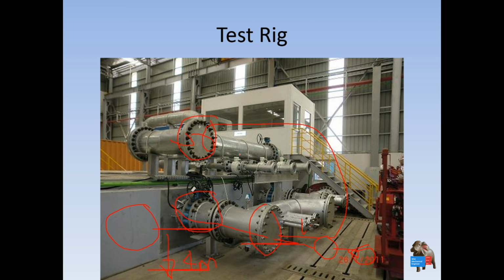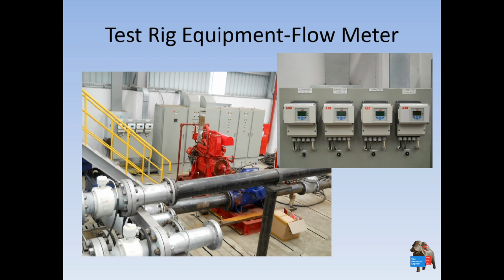As you can see as well, you have some instruments as shown in the photographs. You have here what we call ultrasonic flow meters. A long time ago, before this equipment was used in industry, the flow was measured by the pressure difference at two points, called Venturi meters. But nowadays they use an ultrasonic flow meter at the discharge to measure the flow. This is a clear view of how the ultrasonic flow meter is installed, and this is the display of the flow capacity of water flowing in the pipe during testing. The cable here will be connected to this panel, and during testing you know how much the flow capacity of the pump is.